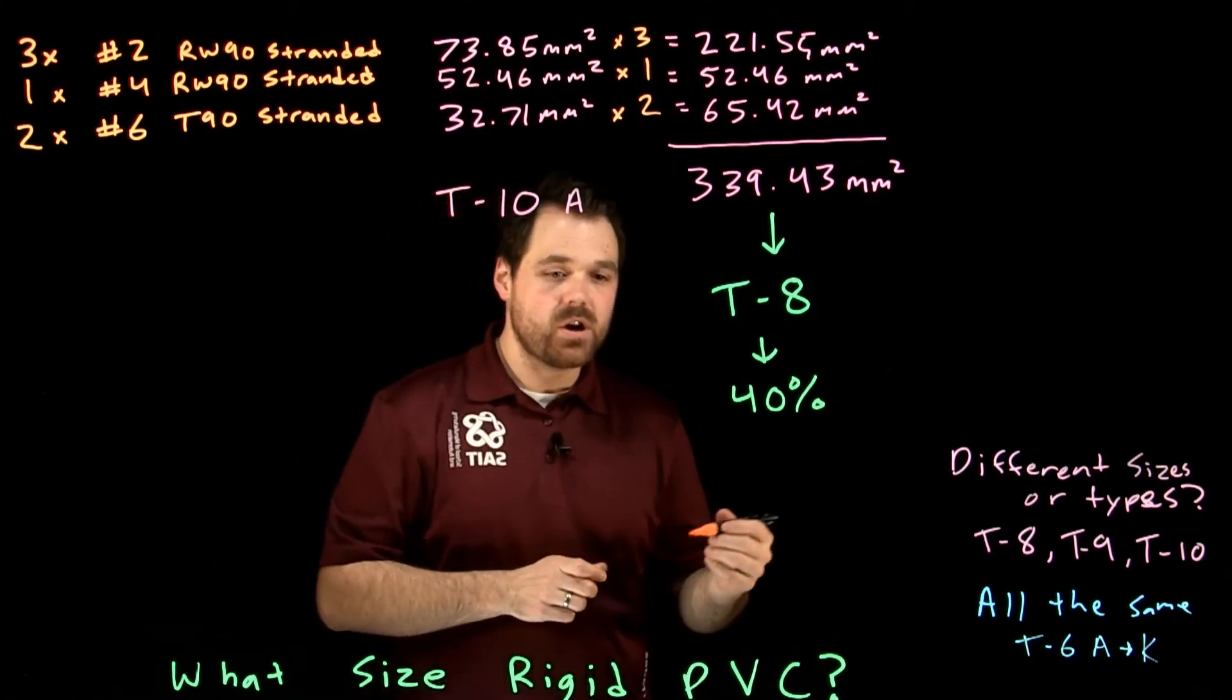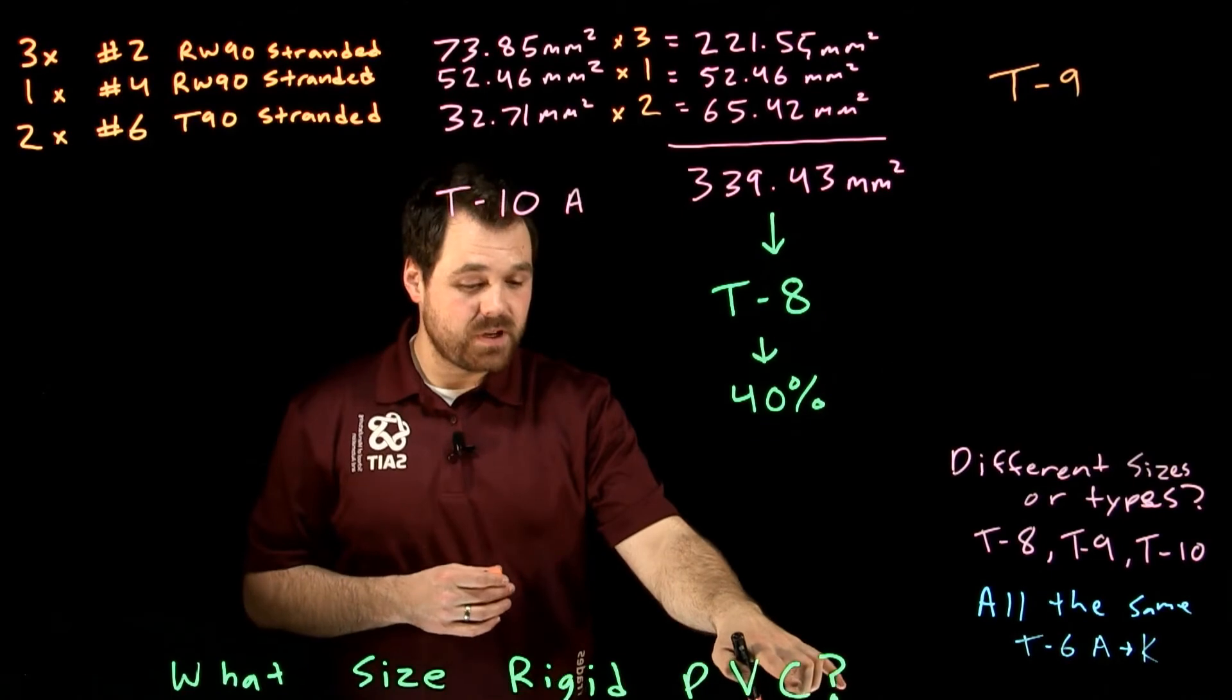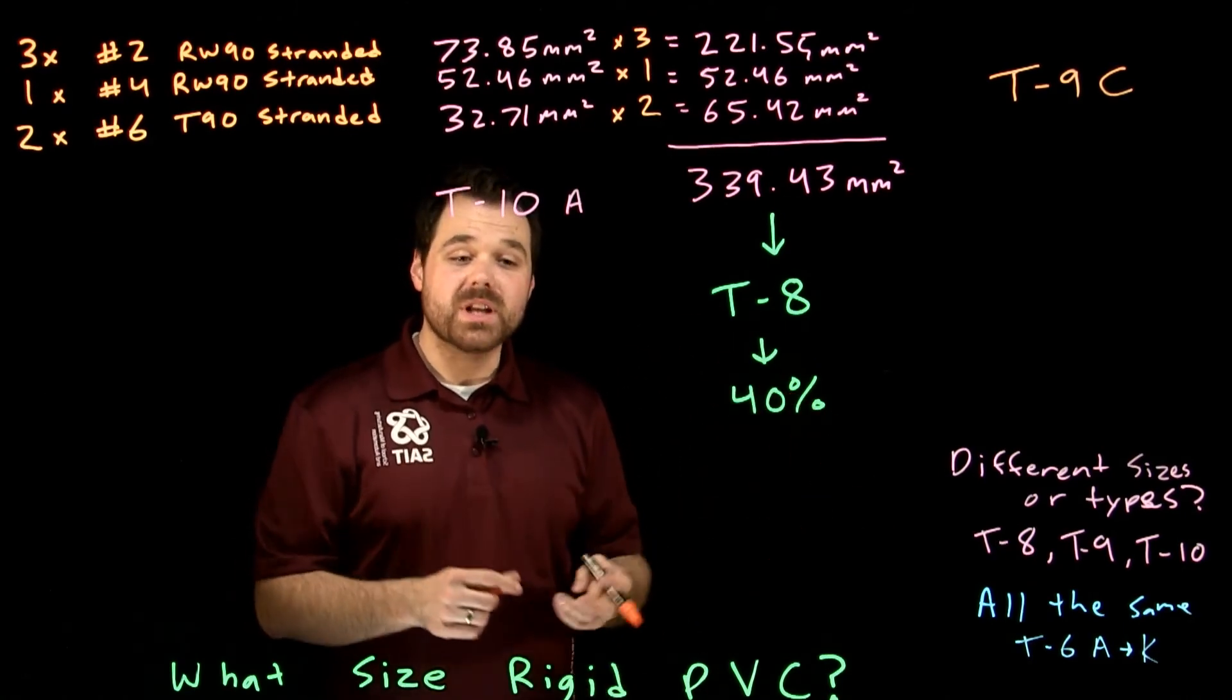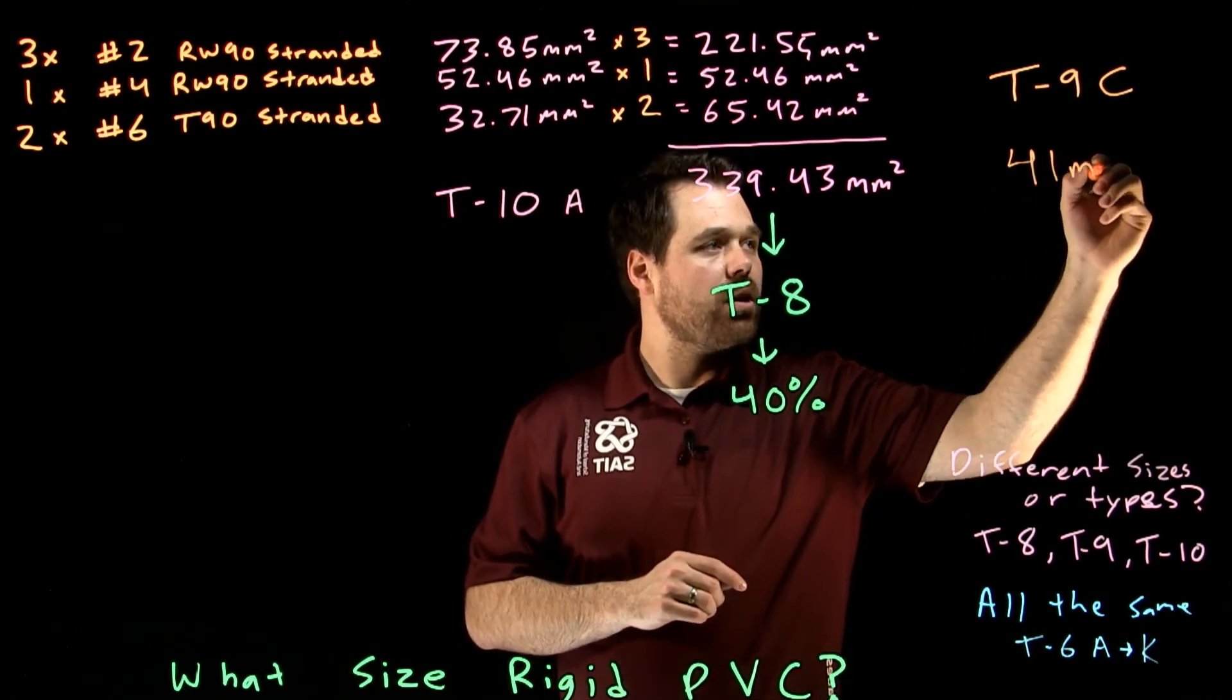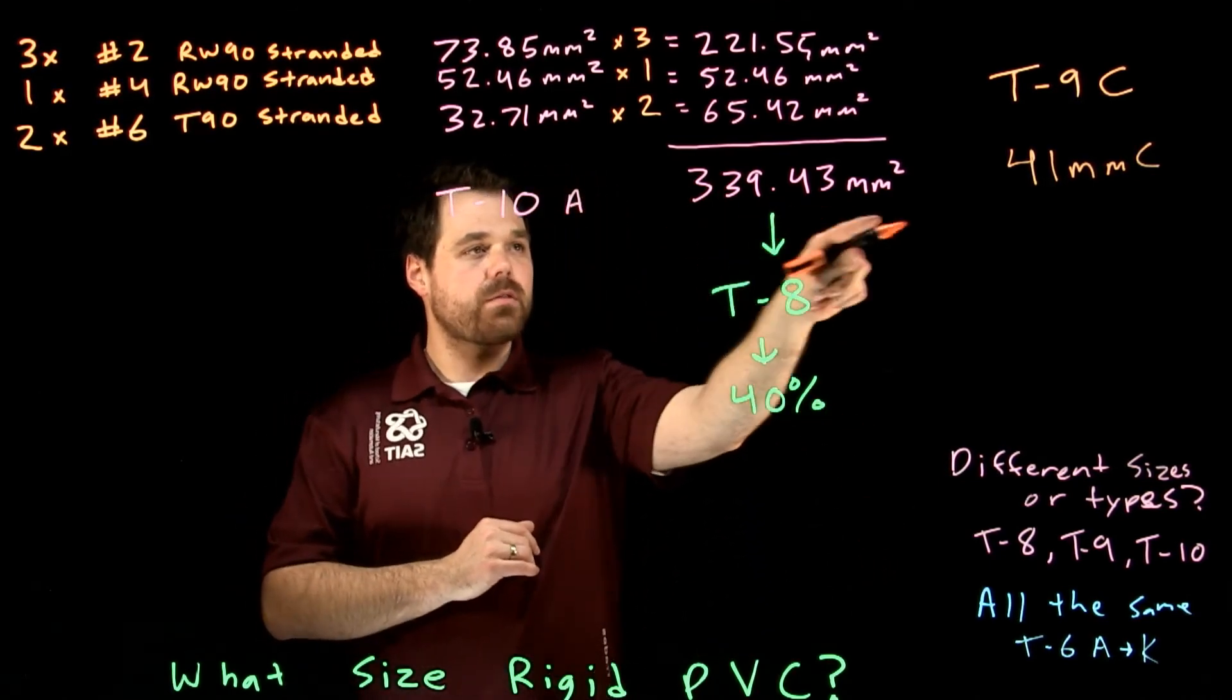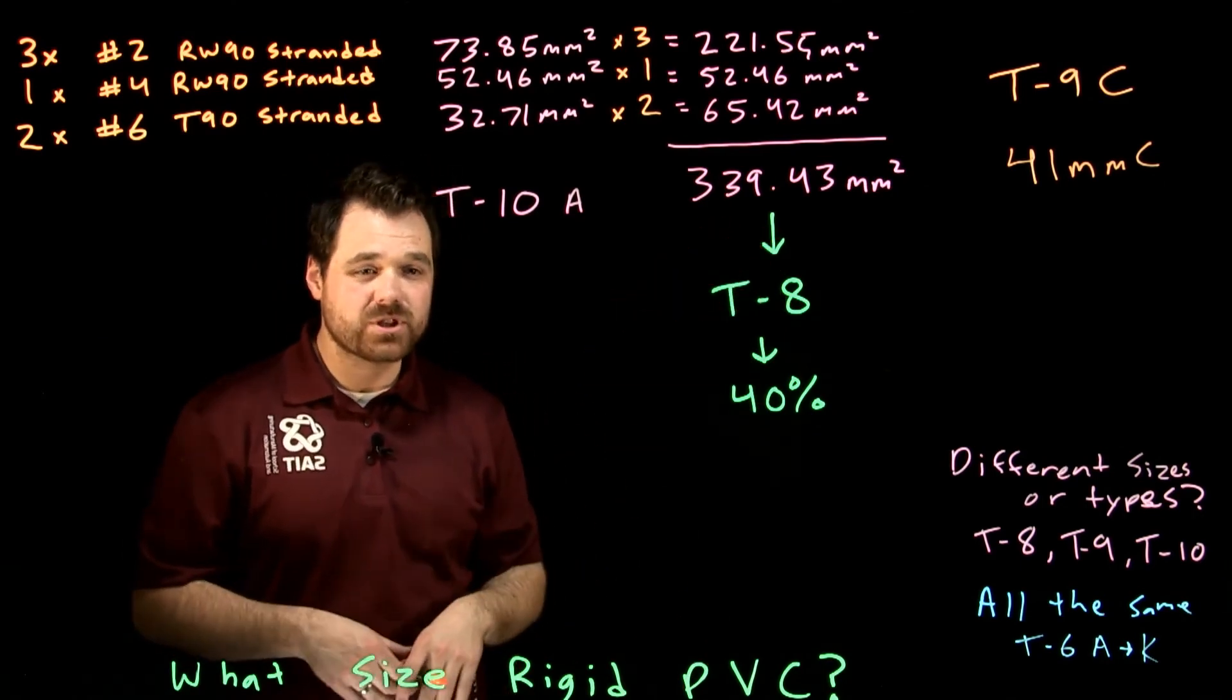Our final stop is we are going to go to table nine. Specifically, because we're looking at for rigid PVC, we're actually going to go to table nine C. Now table nine C talks about rigid PVC. We go to that forty percent column and it tells us we are going to require a forty one millimeter conduit. Forty one millimeter conduit can hold up to four hundred and fifty six millimeters squared. Which means our three hundred and thirty nine millimeters squared is going to fit. If we went to the size below, that wouldn't fit with the forty percent fill.